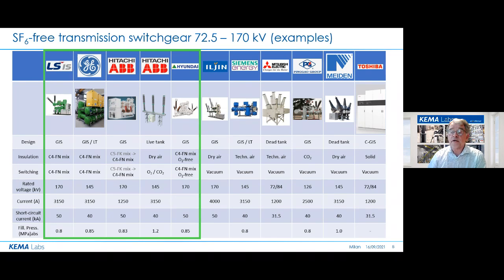First, in the green square, there is one group of products that use the alternative gases for interruption and insulation, as all SF6 switchgear does. Almost all alternative gas breakers now use C4FN mixed with CO2 and O2, while the C5FK option for high voltage seems to be abandoned now. Nevertheless, there is no generally accepted mixture composition.